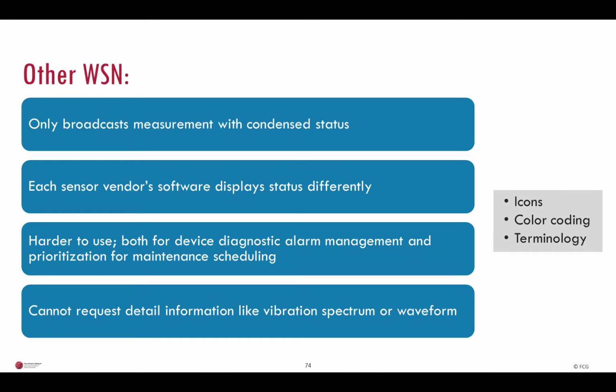As explained, with most wireless sensor network technologies, you end up with multiple heterogeneous systems with the software for each sensor vendor. Each sensor vendor's software displaying sensor status differently. Different icons, color coding, and terminology for the severity of sensor problems. This inconsistency among vendors makes sensors and software for such technologies harder to use, both for device diagnostics, alarm management, and prioritization for maintenance scheduling. So be careful. And some technologies only transmit measurement and status. There's no communication of advanced diagnostics data. That is, you cannot see detailed information like vibration spectrum or waveform because the information is not communicated. Again, be careful.